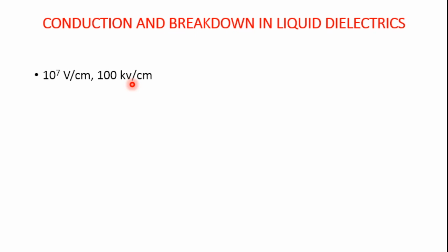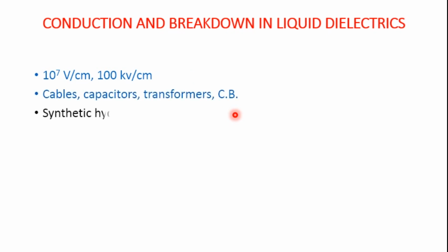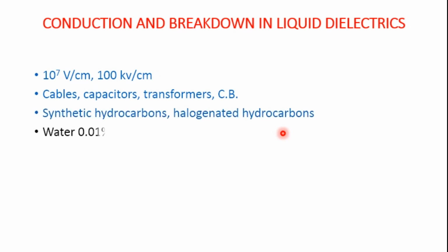This is the reason we choose liquid as a dielectric medium in the case of transformer oil. Although liquids are expected to give around 10 megavolt per centimeter, in practice we may get 100 kV per centimeter. So we use liquid dielectric media in cables, capacitors, transformers and circuit breakers. Petroleum oils are the most commonly used liquid dielectric media. Synthetic hydrocarbons and halogenated hydrocarbons are also used for certain applications.